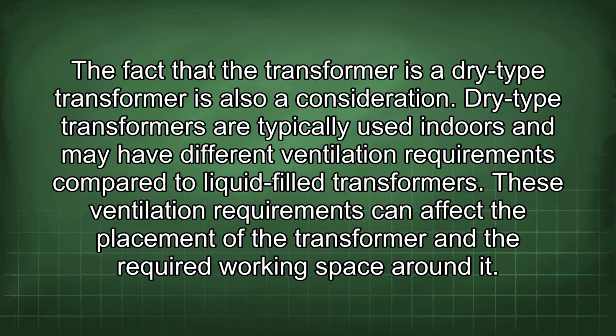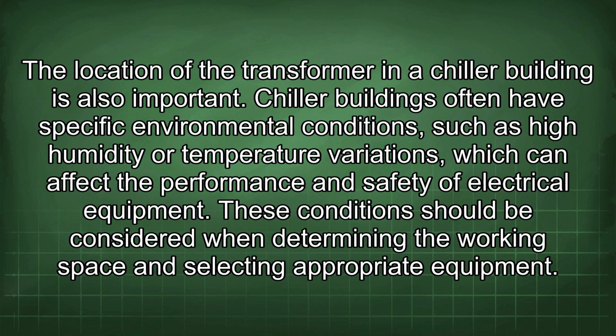The fact that the transformer is a dry-type transformer is also a consideration. Dry-type transformers are typically used indoors and may have different ventilation requirements compared to liquid-filled transformers. These ventilation requirements can affect the placement of the transformer and the required working space around it. The location of the transformer in a chiller building is also important. Chiller buildings often have specific environmental conditions, such as high humidity or temperature variations, which can affect the performance and safety of electrical equipment. These conditions should be considered when determining the working space and selecting appropriate equipment.